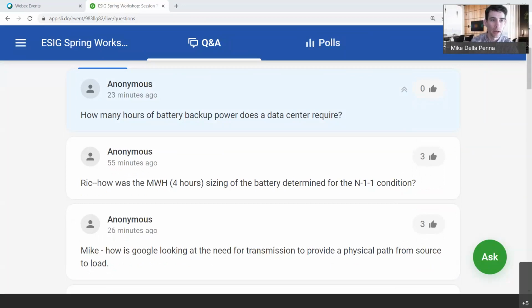As a somewhat limited general industry standard, we install 24 hours worth of diesel fuel backup, as sort of the normal hyperscaler standard. And what we are installing is quite a bit less than that, because you might say, well, that's not going to be very cost effective, and it would be correct to do that with batteries. I'm not able to tell you the precise duration - it's pretty short. But what we are looking at is really a combination of the battery with an intelligent software layer that's taking a look and saying, okay, when there is an outage on the utility side, let us run on the diesel generators plus the batteries for some period of time.